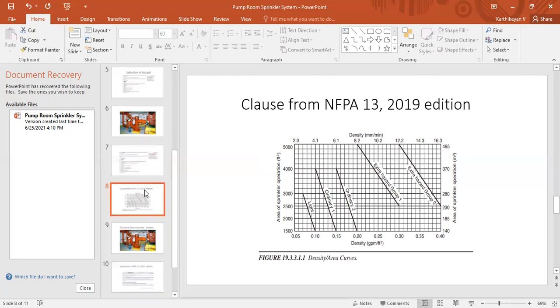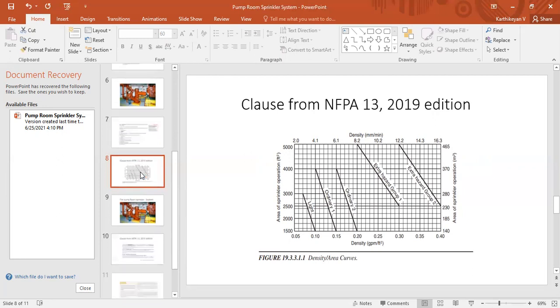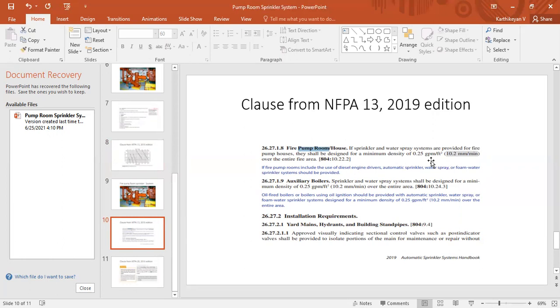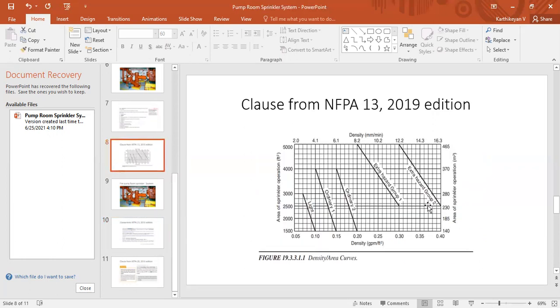Back to the question: what is the hazard of fire pump room? What NFPA 13 says? In NFPA 13, it not directly says about the hazard. What it says is, if fire pump room we are using for automatic sprinkler system, we have to use 10.2 lpm per square meter as a design density. If it is 10.2, if we check here, it will come under extra hazard group one. So fire pump room hazard is extra hazard group one. Is it correct?